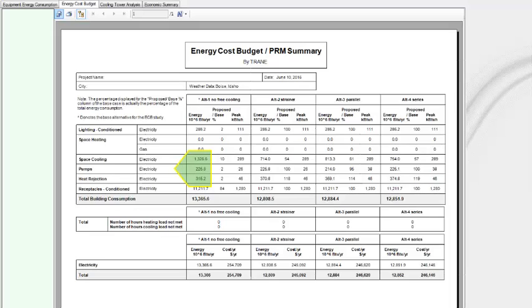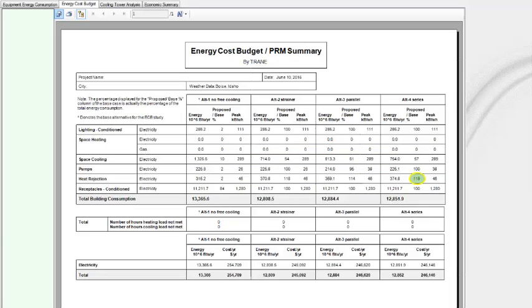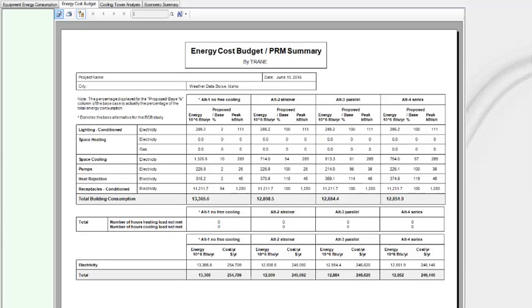Notice here that the consumption for cooling equipment, pumps, and heat rejection are all separate line items. The sum of these three line items is what must be compared to determine the savings resulting from adding free cooling to your design. While the total building savings in this example is around 3.5% to 4% for the heat exchangers, we can see the chiller electric use is reduced significantly for each of the free cooling methods. Note that the heat rejection for the series-configured unit is 119% of the no-economizer version in Alternative 1. The nice thing about the ECB report is that all the numbers are in one spot. Alternative 2, the strainer cycle, had the greatest energy savings, with the heat exchanger configurations right behind.